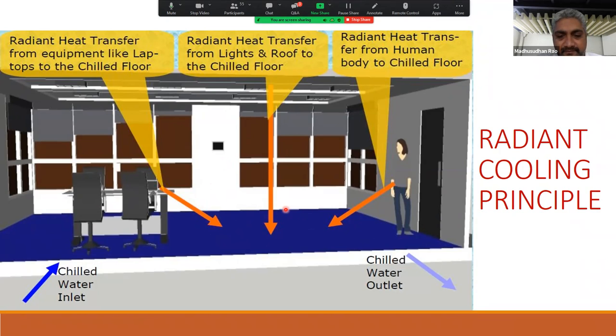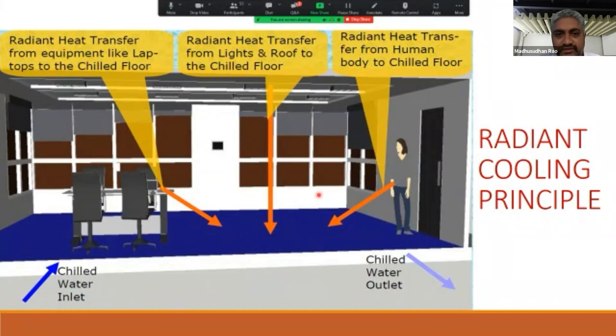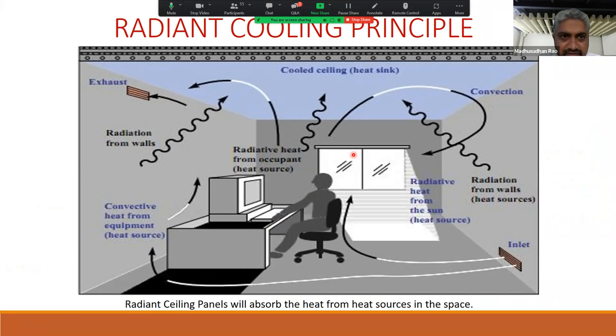will take away the heat from the space. Okay, so a typical installation would be to embed pipes in the floor, and you supply chilled water, and this entire floor acts as a heat exchanger and takes the heat away. All these heat sources that you see, human occupant, the lighting, equipment, all can radiate heat to this heat sink. And that's how the heat is taken away. The same thing can be done by having the heat sink on the ceiling.